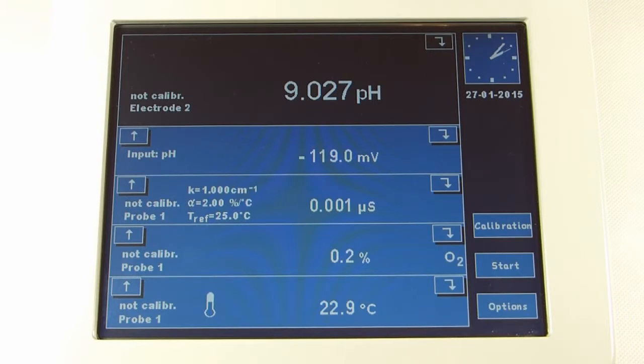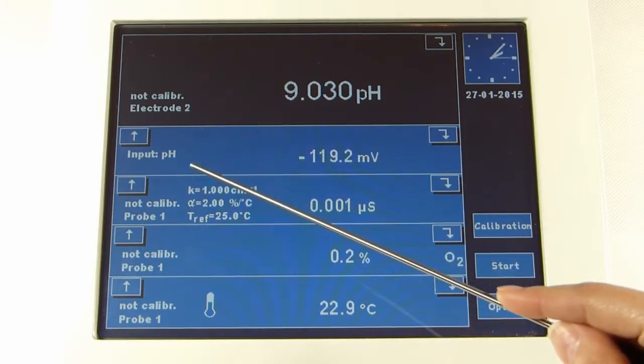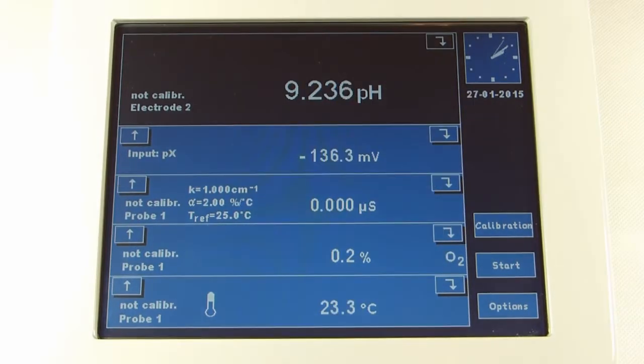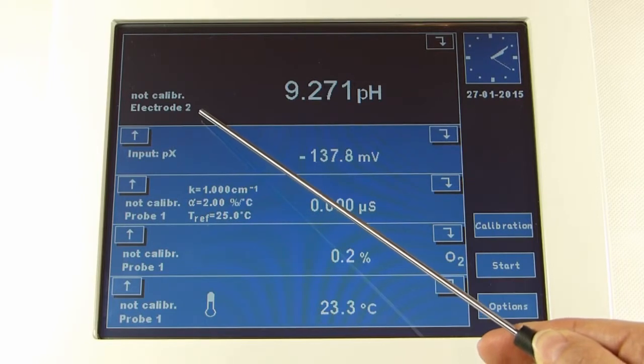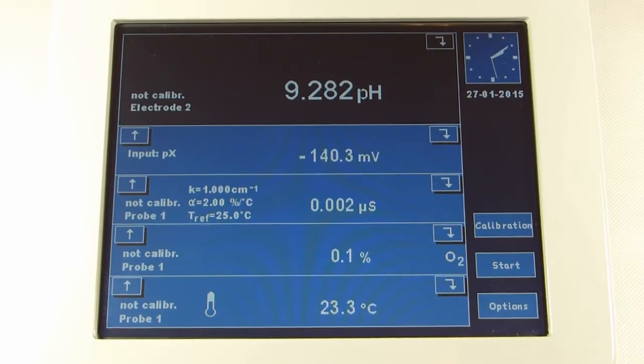Next to the reading, in each window, we can see the basic parameters set by the user. It is possible to store calibration results for 3 electrodes, cells or sensors. The electrodes should have the numbers given before the calibration. On the left, next to the reading, there appears one of 3 symbols, electrode 1, 2 or 3, which corresponds to the chosen electrode. Such a solution enables fast replacement of a broken electrode or changing it to other type to adjust it to measured substance. After replacing the electrode, the measurements may be continued and time saved.